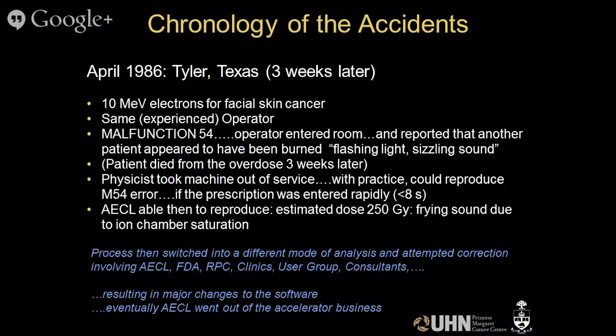The machine was taken out of service, and the physicists and the operators really tried to reproduce the error, and eventually managed to get it to happen if this prescription was entered very rapidly. So if you could type fast enough, you could make this happen. The frying sound was put down to the saturation of the ion chamber, so there was like shorting across the ion chamber, with an estimated dose of 250.